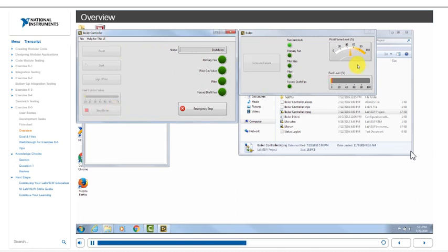Here we can see our pilot flame level decrementing. We're in a shutdown state. Our primary fan LED turns on for 2 seconds, then it turns off, and we're in our lockout state. The reset button has been enabled. Our UIs now match the state that they were in when we first started the application. And in fact, we can restart the boiler now and walk through the entire cycle again.